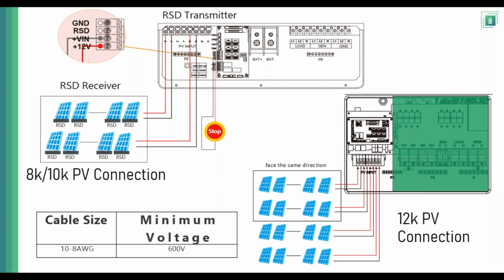So on the 12K, the first MPPT can withstand up to 25 amps, okay? And then the second and the third MPPT can withstand up to 15 amps, okay? We would use cable 10-8 for this installation.